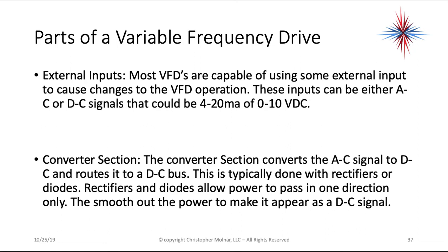So we have two sides of it usually. We have a positive and a negative. The positive side takes the AC input signal and only passes the side that's on the positive side of the sine wave. The negative side passes the side that's on the negative side of the sine wave. So on the DC bus, I have a true positive and a negative supply.